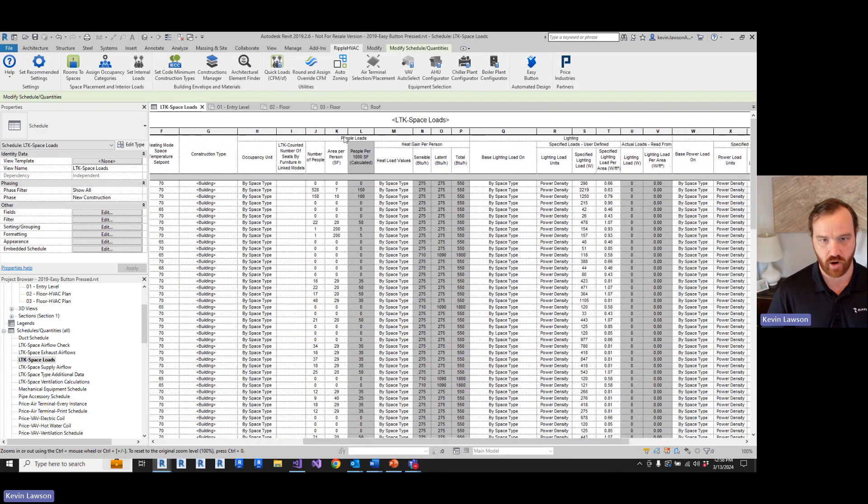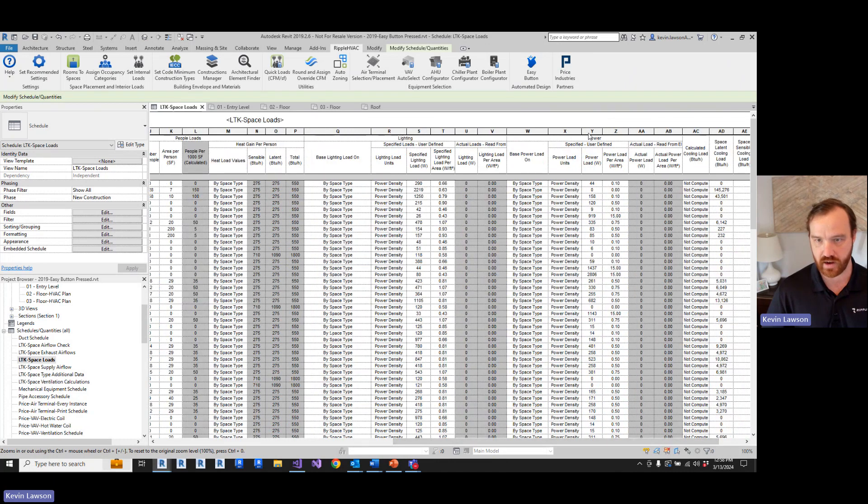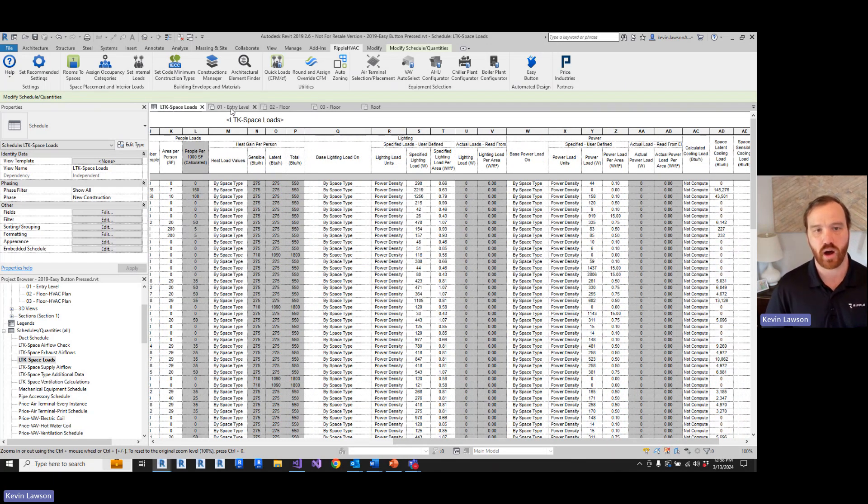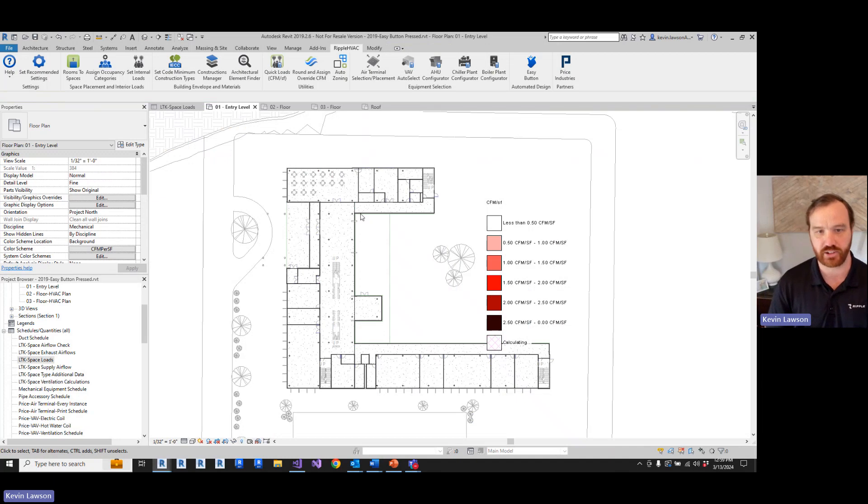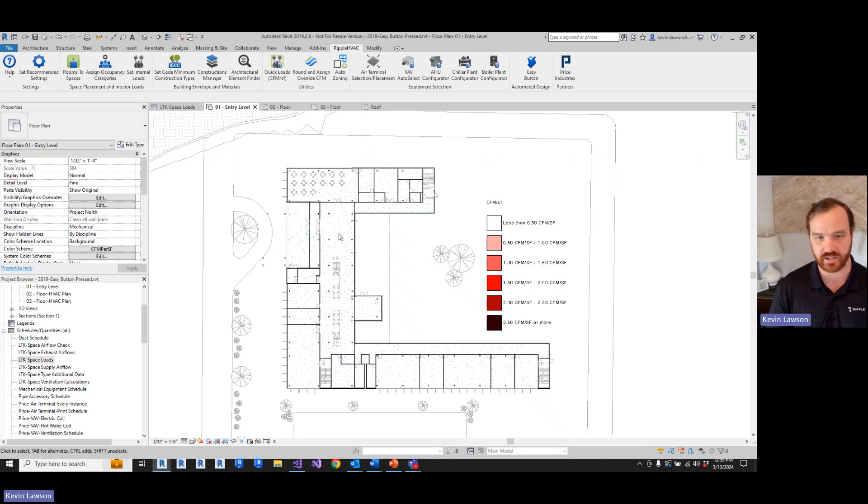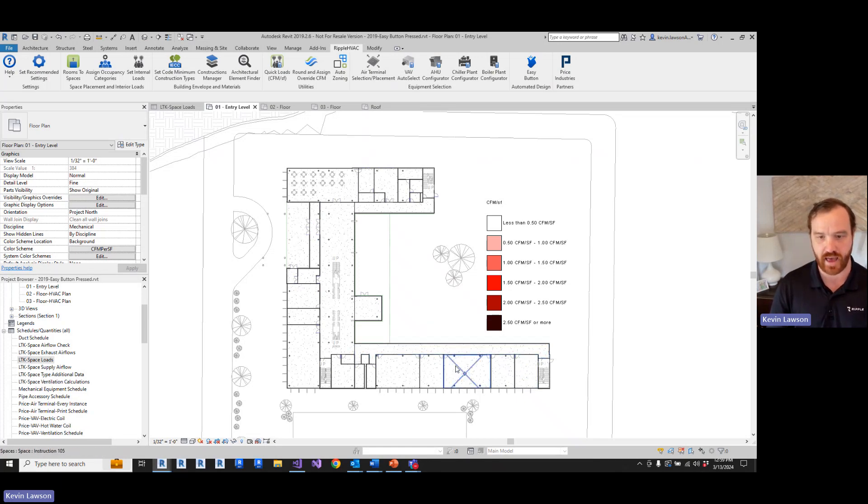So we've got our people loads based on the space type, we've got our lighting loads based on the space type, and we've got our power loads based on the space type. A traditional workflow would be that an engineer would take the total square footage of the building, apply a CFM per square foot and start selecting equipment based on that.